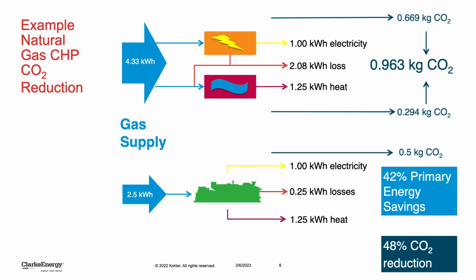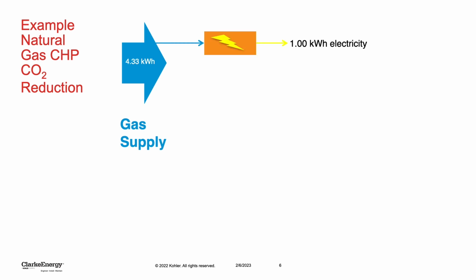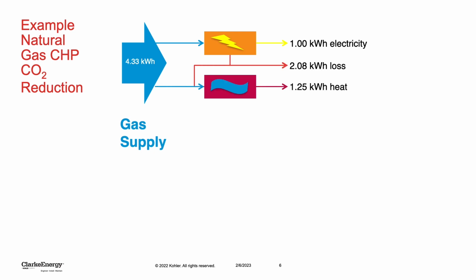This is an example of how a CHP engine can provide tangible electricity and carbon savings versus the separate purchase of electricity from the grid and gas utilized in a boiler. In case one, 4.33 kilowatt hours of energy input into a system drives 1 kilowatt hour of electricity, 1.25 kilowatt hours of heat, but you have an overall loss of roughly 2 kilowatt hours.